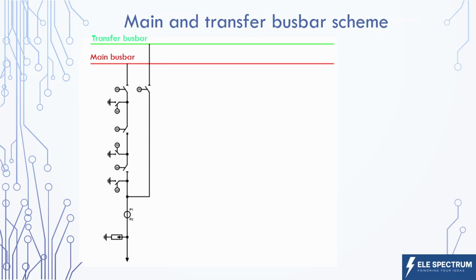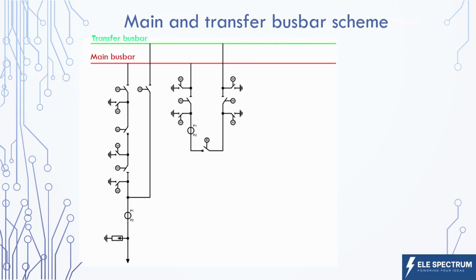And for this purpose, we need one additional bay, which is called the transfer bus coupler bay. And this bay consists of a circuit breaker, disconnector, earthing switch, and CTs, as you can see here on your screen. Now, the main question is how to divert the power through the transfer bus coupler while the feeder is on, and that too without interrupting the power supply. For this, let's recall how a circuit breaker and a disconnector operate. So a circuit breaker has the capability to interrupt or connect the power supply, while a disconnector does not have this capability.